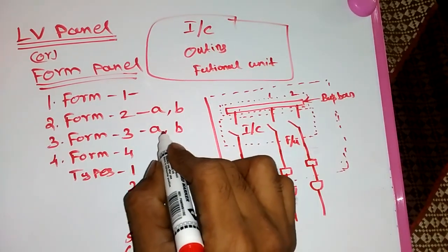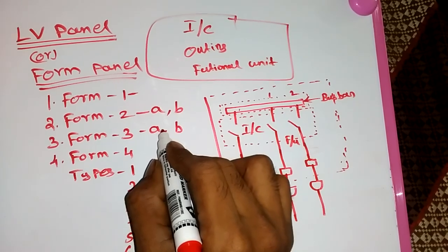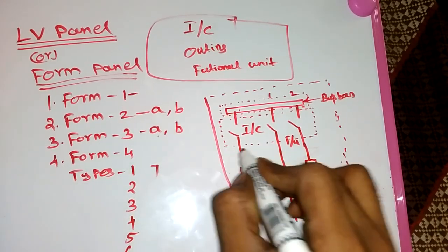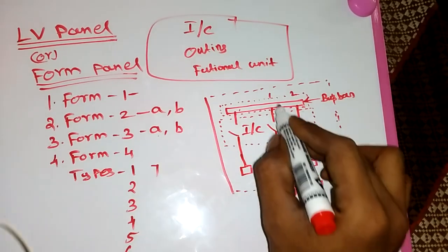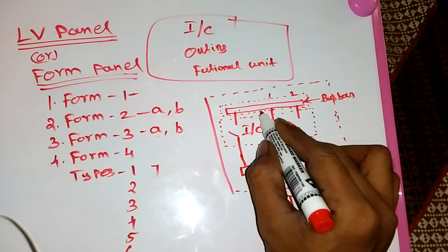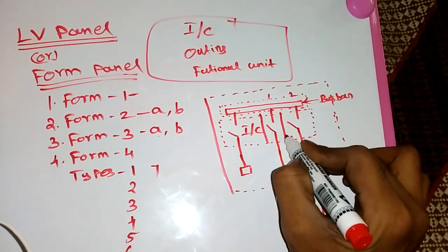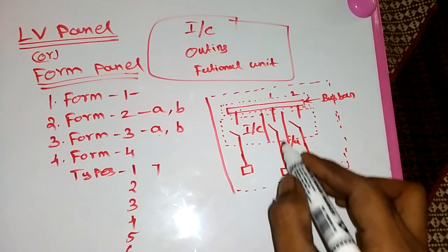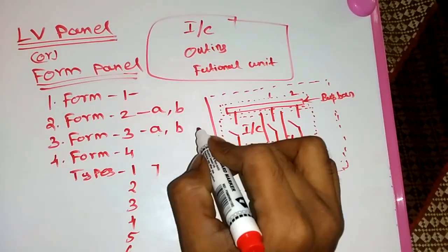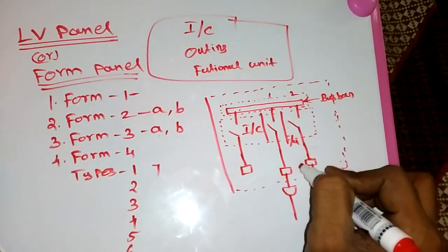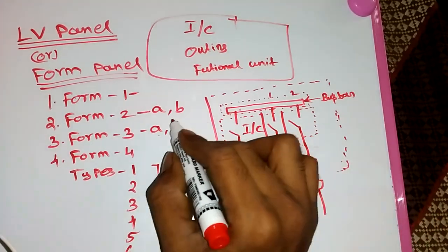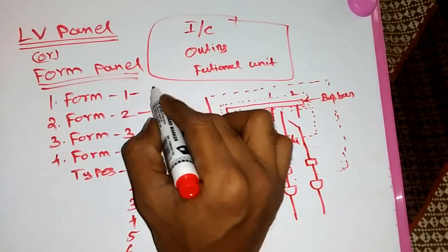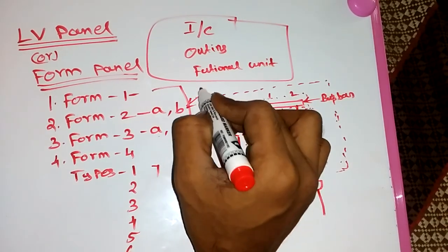In Form 2 Type B, the bus bar also has some separation, meaning the bus bar has a separation, the incoming and functional units have separation, and terminals also have separation — but not from each other's functional units. Mostly in Form 2 we make SMDBs and small main DBs. Then we go to Form 3, which has two types: Type A and Type B. In Form 3, we separate the same way, but we also separate each functional unit from one another.